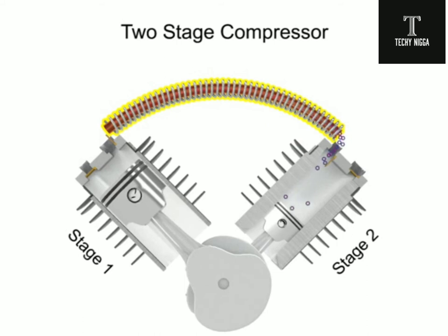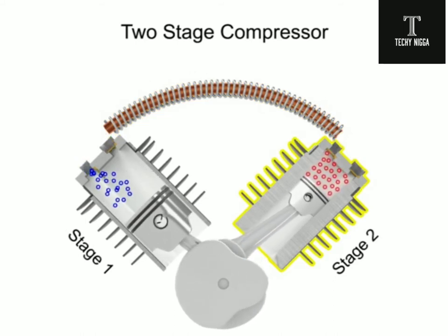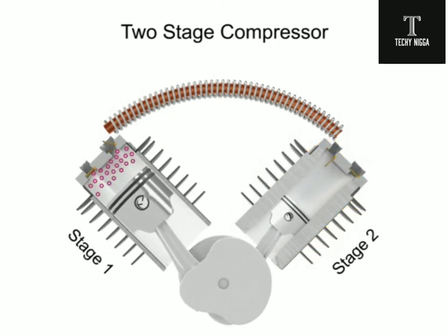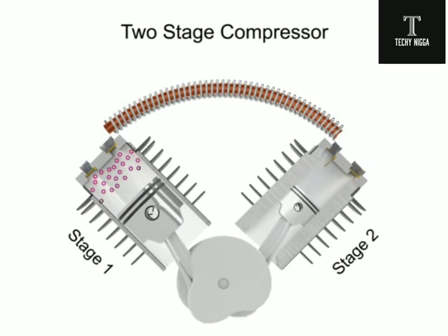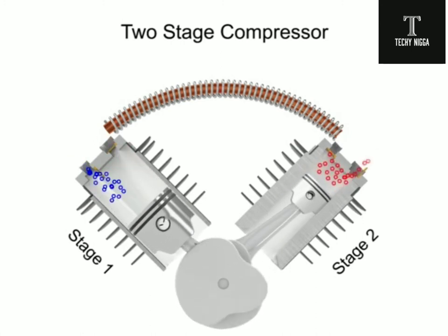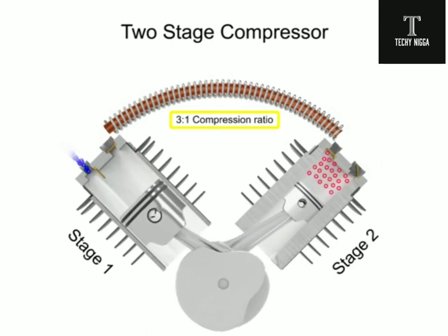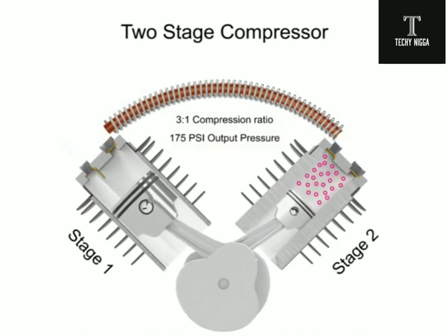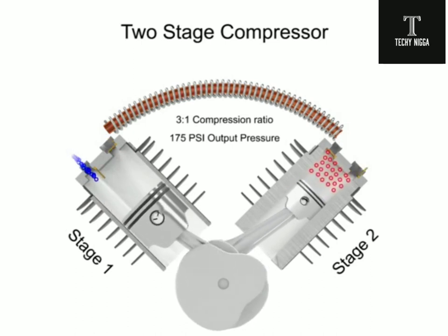After the air is cooled within the tube, the compressed air enters the second stage to be compressed even further. The compressed air entering the second stage is sometimes called supercharged air. Two-stage compressors have a compression range of 3 to 1 or even less per stage, but can operate up to 175 psi. They can also deliver more air at a higher pressure than single-stage compressors of the same horsepower.